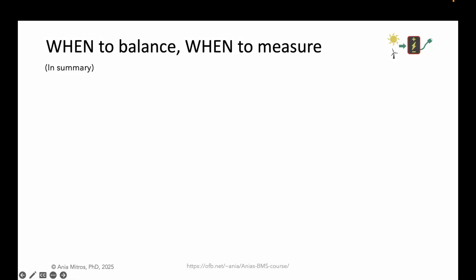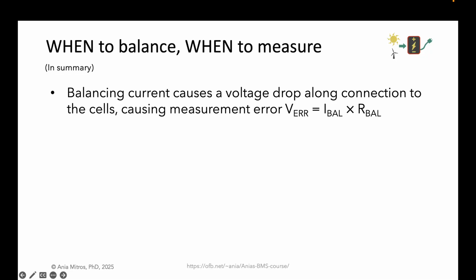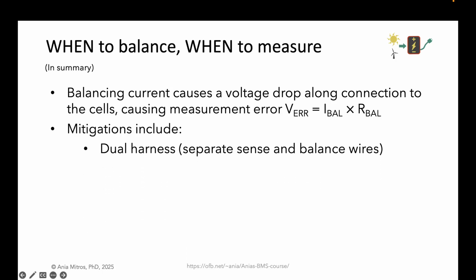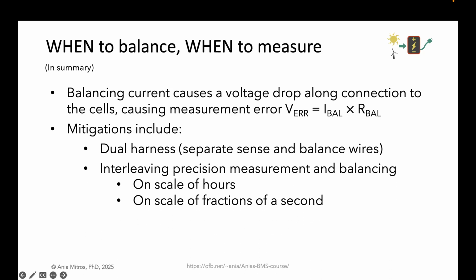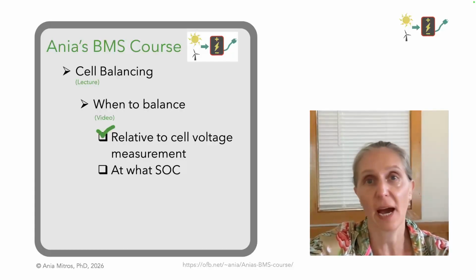Let's summarize the key points in this section. Balancing current causes a voltage drop along the connection to the cells, causing measurement error equal to the product of the balancing current and the parasitic resistance between cell and sensor. Mitigations include a dual harness with separate sense and balance wires, though in practice, cost and mechanical complexity are significant hurdles. Interleaving precision measurement and balancing allows for precise measurements when balancing current is not flowing. This can be implemented with the interleaving on a timescale of hours, or fractions of a second, or both. Firmware compensation can reduce the residual error, and this is inexpensive to implement, but may not be sufficient on its own. Having discussed how to interleave balancing with accurate cell measurements, let's discuss at what state of charge to balance.